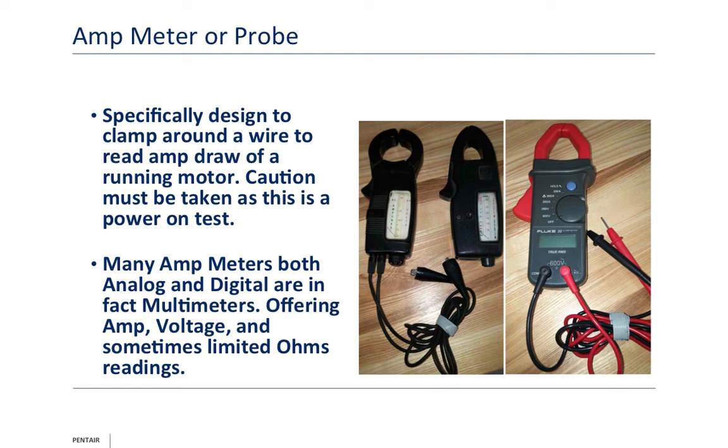Now, a lot of guys say, why even show an analog with the needle swing versus the digital? The digital is so much more accurate. Well, a few things. One, if you're working with a lot of three-phase motors, I like clamp-on meters that are voltmeters and ampmeters because the needle will fluctuate and it doesn't have memory. For example, if I have a wild leg on three-phase power that I'm trying to track down, I can do it easier with an analog meter. I've been in instances where we've taken three analog meters and put them on each power leg coming in, so we can monitor the voltage on each leg independently. Why not use a digital? Because too often digitals will sample for a period of time, and then they lock in a number, or they average the number for you and don't keep reporting. So analog ones are very visual, and they don't have that memory issue.